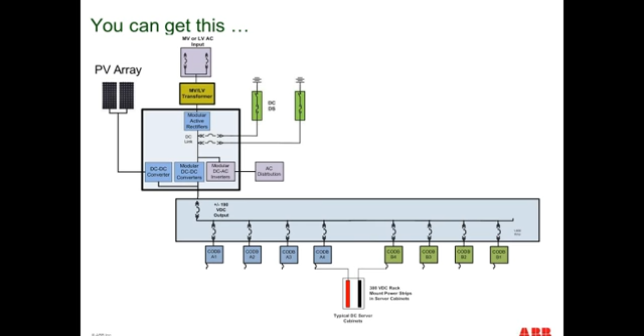A DC topology also allows us to take a standard power supply architecture—where the front end of a server has a 277, 120, or 240 volt rectifier—and simply remove that from the power delivery stream. When you remove that component from the server, a number of things happen. First, with a constant voltage output in the system, you can use a 380 volt DC power supply that's significantly more efficient than one with a variable voltage input window, because you can optimize the components around a very tightly held voltage. Second, from a reliability standpoint, your parts count in the server goes down, so in theory you get increased reliability.